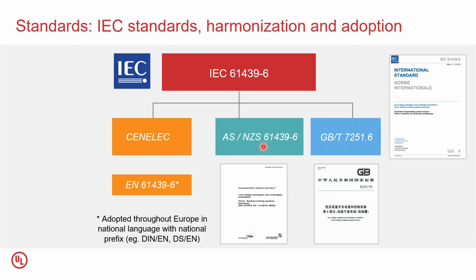Similarly, Australia and New Zealand have also harmonized their national standard with the 61439-6, but it has come out with a separate naming convention. That is because there are probably a couple of national differences that are applicable primarily for Australia and New Zealand. Similarly, China has harmonized its busway standard with IEC 61439 and does contain a couple of national deviations. So the IEC 61439-6 is such a popular standard that more than 40 countries across the world have either adopted it or used it as it is in order to specify the requirements for busways.